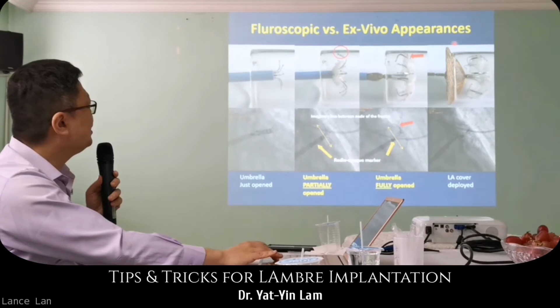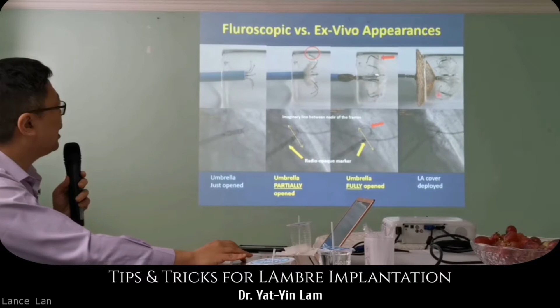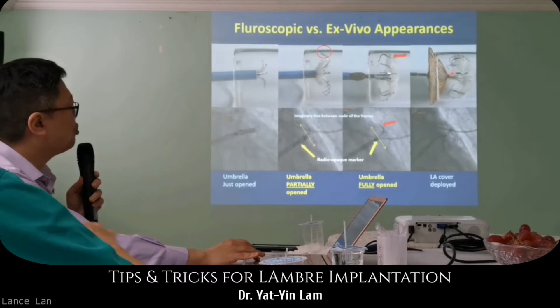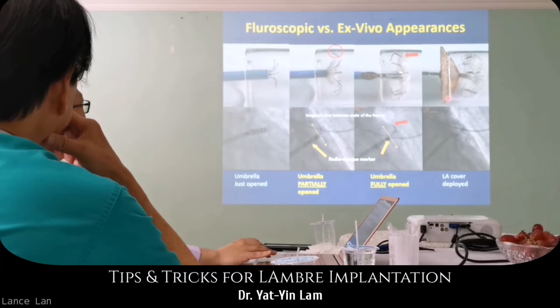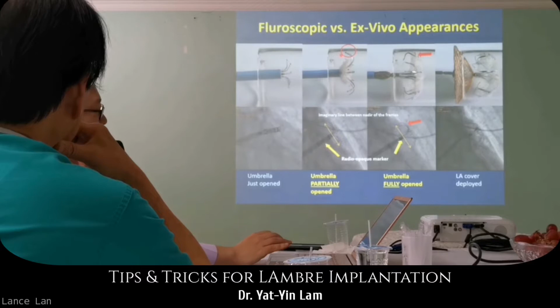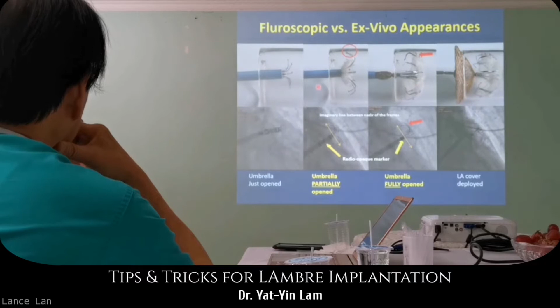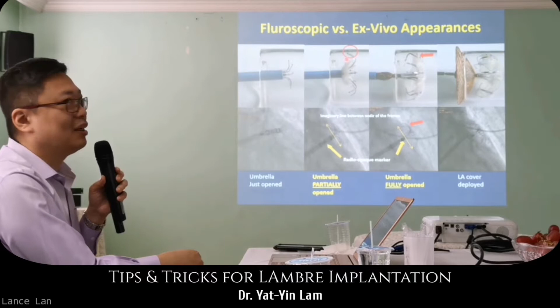And this is a fully opened umbrella. You see this radiopaque marker here, and this is the lower end. They are nearly at the same level. By doing that, the in-sucking force will be better and you will have a better seal. Why do I emphasize this? There's also another safety concern. You see, with a fully open umbrella the covered membrane is in touch with the umbrella. This is good. If you open the umbrella only partially and then just unsheath to bring out the cover, it will also get trapped somehow in the appendage and still be stable, but once you release the cable, maybe the cover will just fall outside. You have a big leak, and I think this will also be associated with more erosion, because you have the metal part keep touching the appendage.